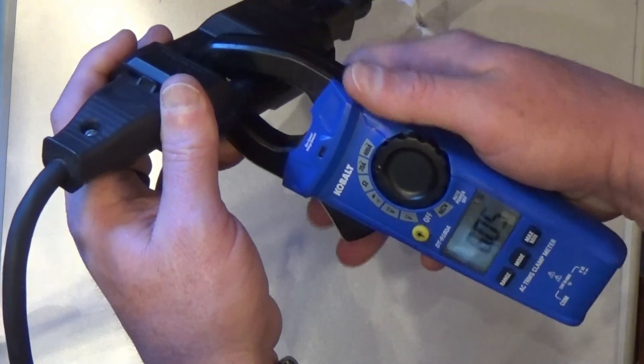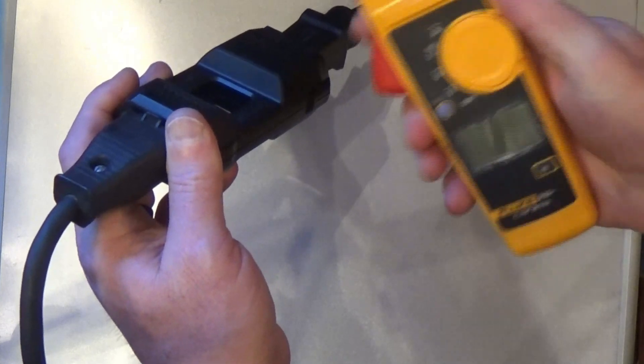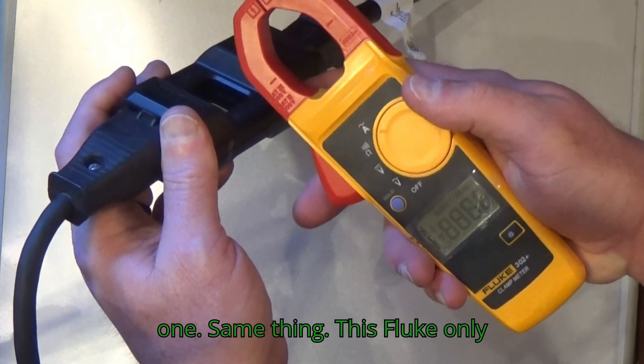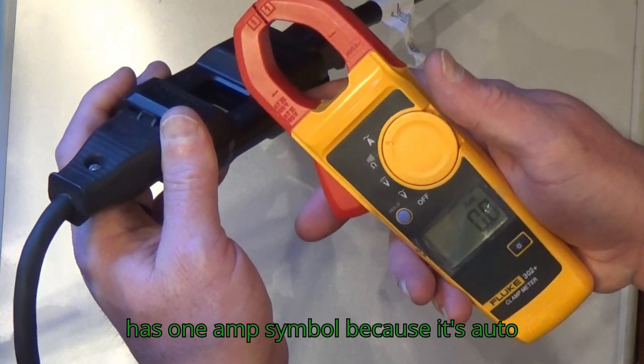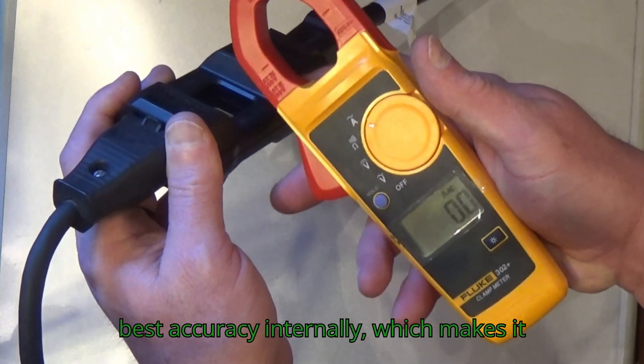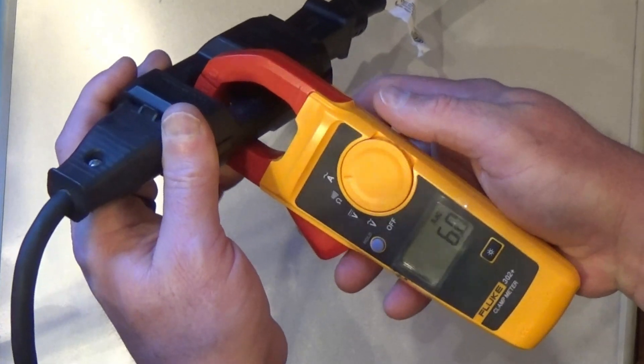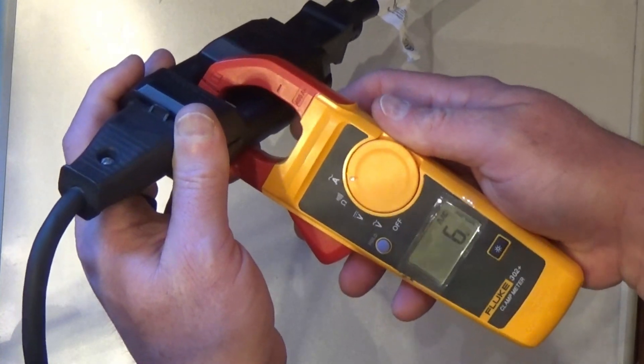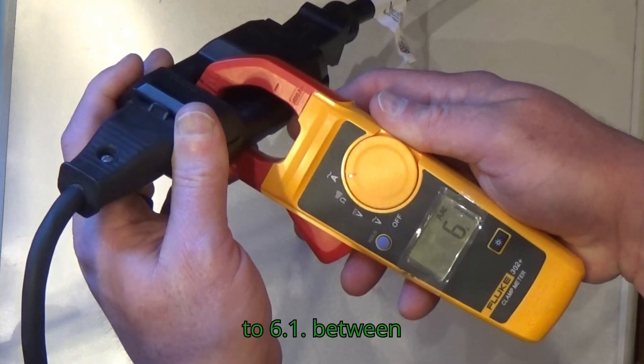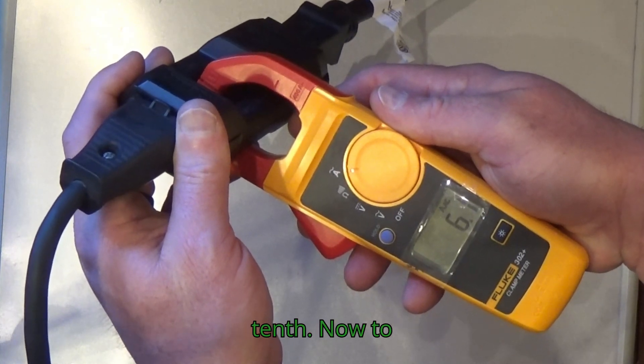Now let's check the other one. Same thing. This Fluke only has one amp symbol because it's auto-ranging. It will range to the best accuracy internally, which makes it really nice. And you can see it's only showing a tenth. There's 6.1. So between the two, there's a difference of about a tenth.